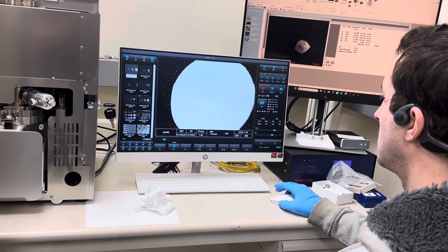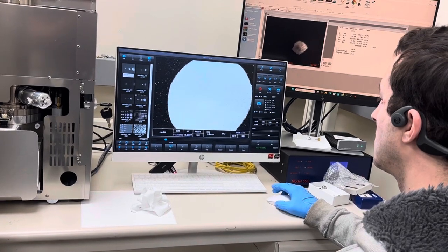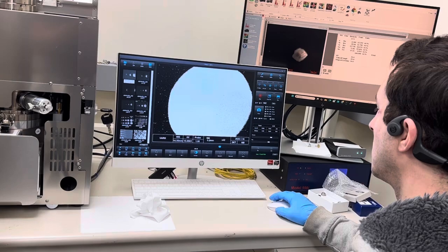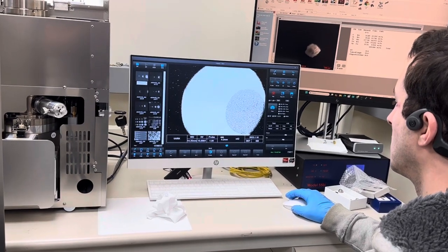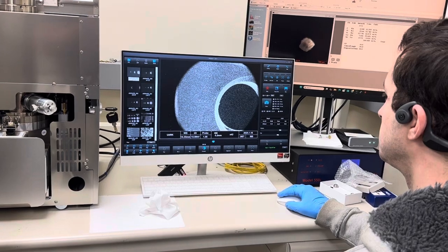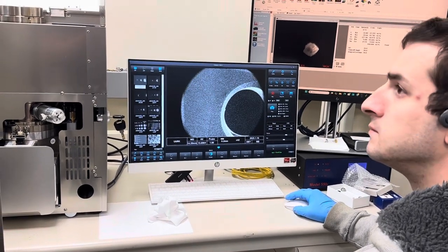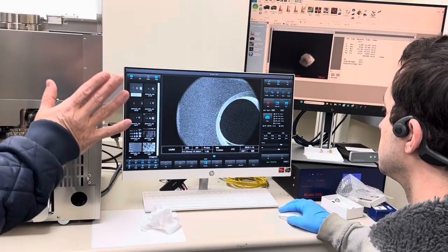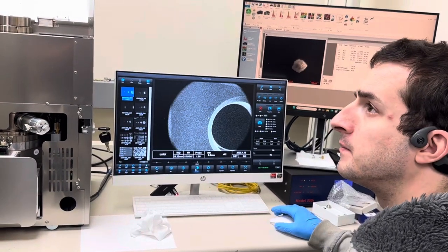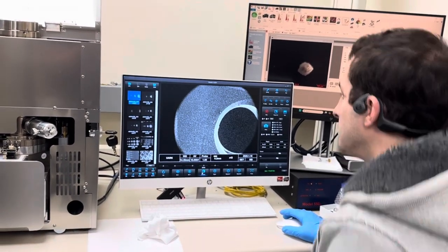All right, so now it's too bright. We can't see what's happening. So left click your mouse, get out of that, and lower your contrast a little bit now. Because when it's too bright, you can't see what's happening. So you want to lower your contrast, which is video, which is photomultiplier tube noise. It didn't have to be that dark, but that's fine, as long as you can see. If the screen is bright white, you can't see anything.